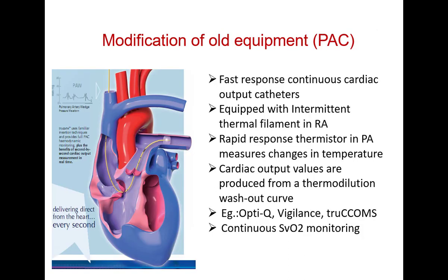So how do we modify an old device? Well, we can revamp the device, add more channels, make it more fast response to cardiac output catheters. If we have, not exactly real time, but a renewal of the data within every 30 seconds from a pulmonary artery catheter, it almost works equivalent to a monitor which can be giving you real time data at the bedside.